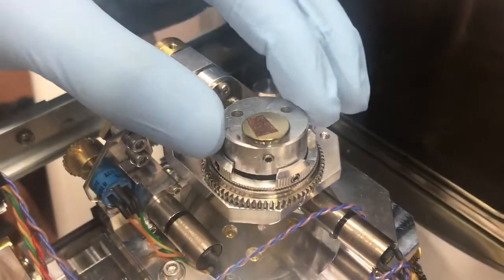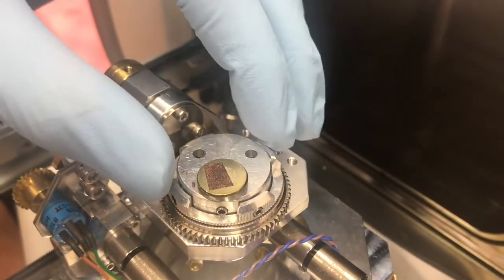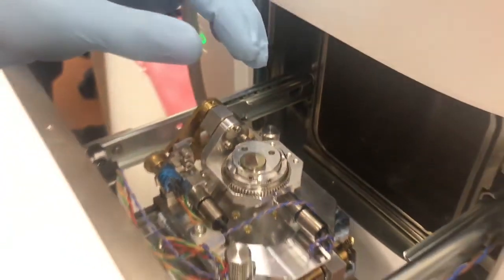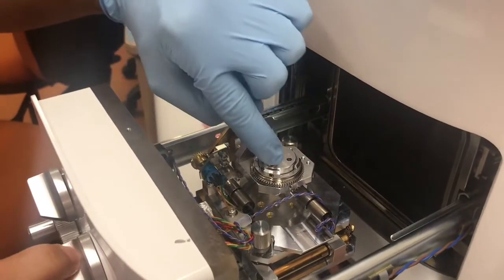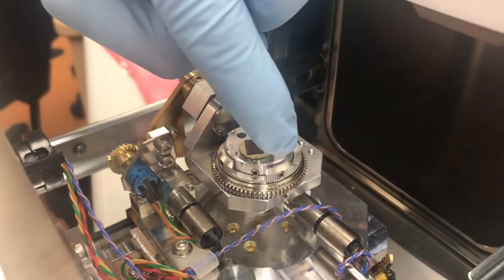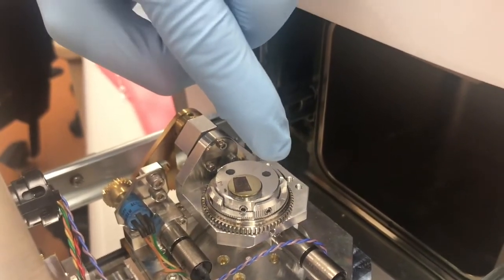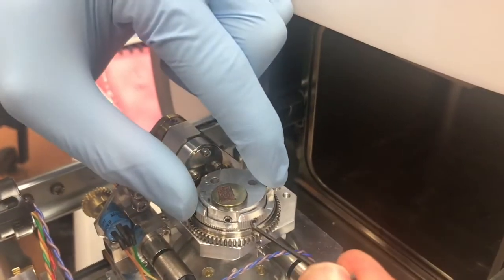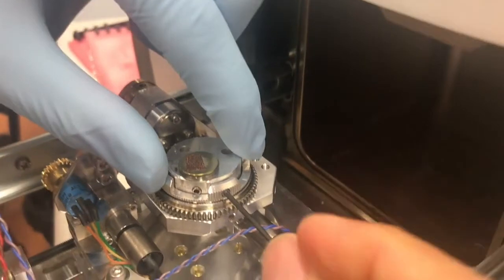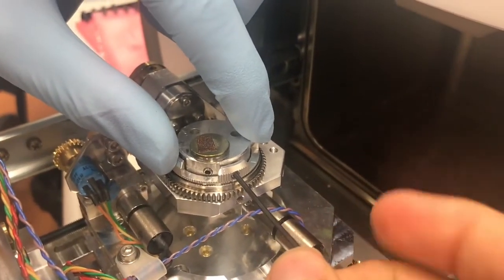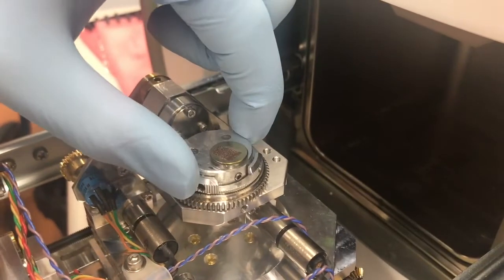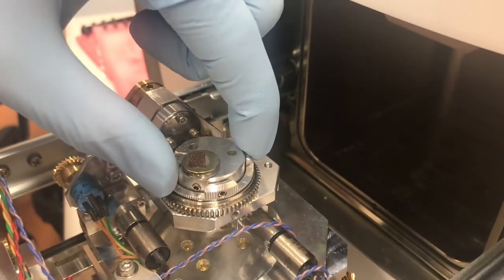Place the sample onto the SEM stage and locate the side hex socket. You may need to rotate the stage using the top right dial in order to see it. Tighten the hex socket gently to secure the sample holder to the SEM stage. The locking ring may also need to be turned clockwise to secure it.